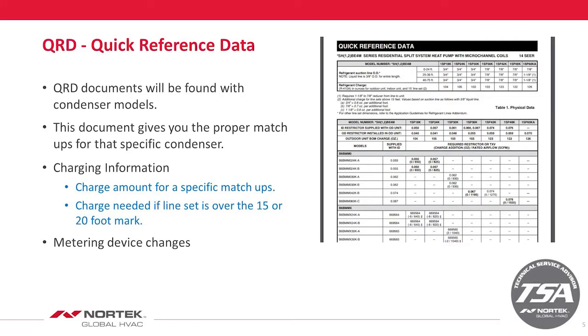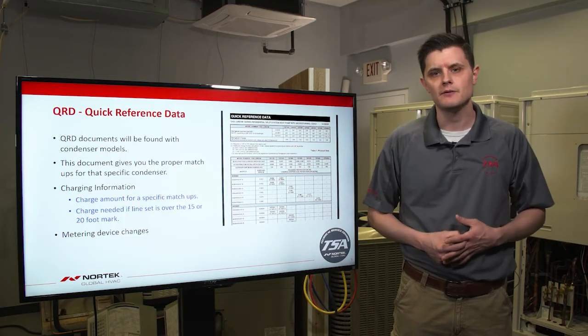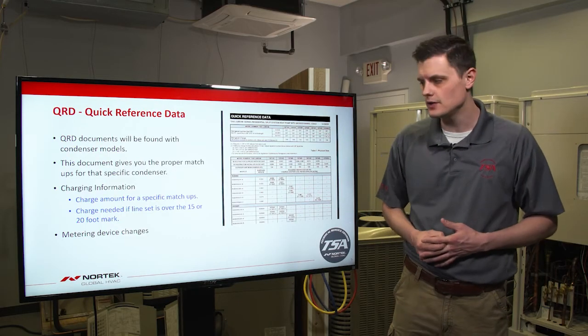The next thing we'll look at is our QRD document. The QRD document is found in each of our condenser models, but we also post it on our literature library if we're going to a job site after that equipment has been installed. The document gives you a proper matchup for that specific condenser and also gives you charging information—the charge amount for that specific matchup, because if you have a two ton paired with a two ton, you may actually need to add an additional amount of refrigerant, and that will be found on the QRD.